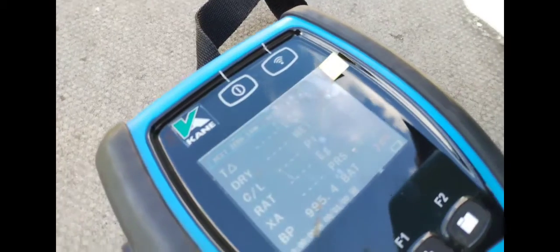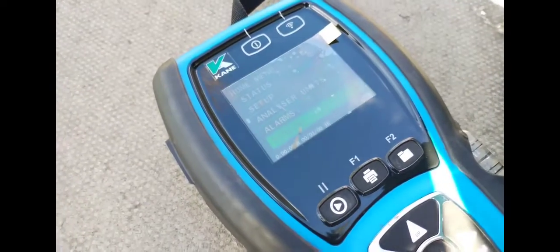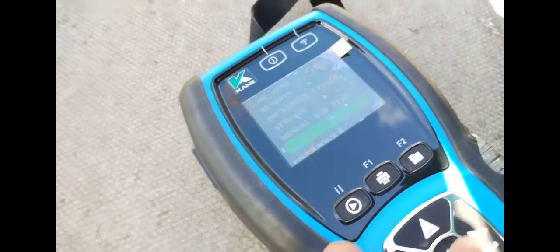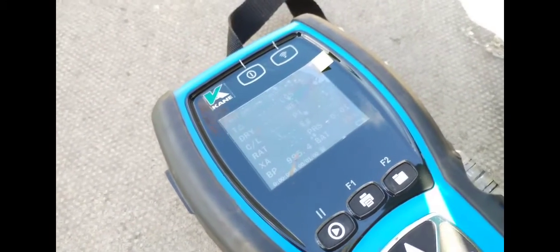Look for your ventilation in your gas meter cupboard and make sure that the meter is stable. I'm going to zero my manometer. Okay, so it's been zeroed. Whilst you're turning things off, just check the condition of the meter, check the housing that it's in, make sure that it can be locked and that it's clearly labeled.